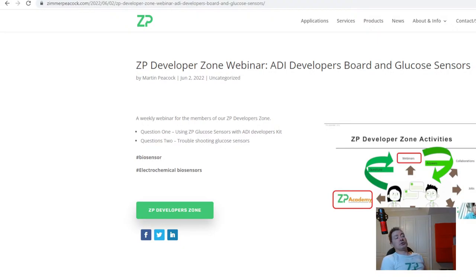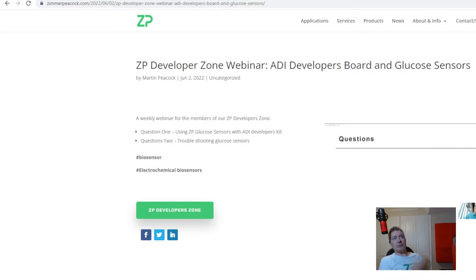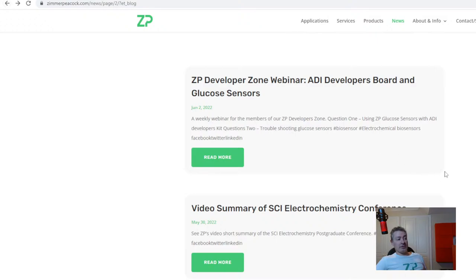We also had another client who was struggling to get linearity with their glucose sensor. What was happening was they had no signal at zero millimolar baseline, a response at around two millimolar, but then no further response beyond that. We gave them advice on how to get more signal and more linearity out of their sensor.